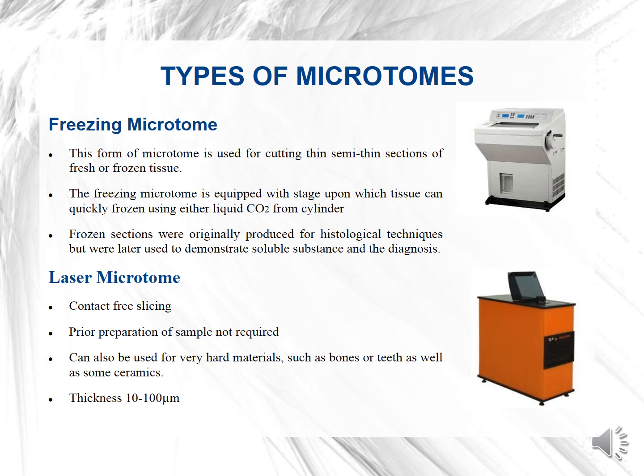Next is the laser microtome. This is the most advanced microtome. It is contact-free slicing, and prior preparation of the sample is not required. It can also be used for very hard materials such as bones or teeth, as well as some ceramics. Thickness is 10 to 100 μm.